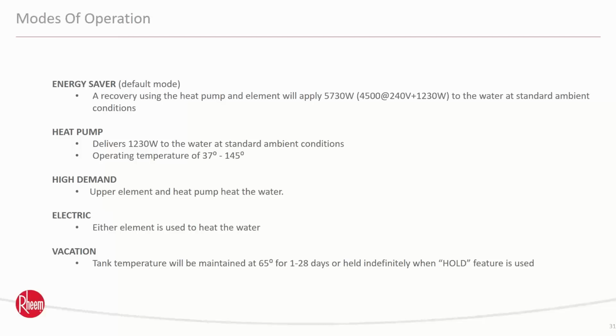The other thing is vacation mode. This thing will hold and maintain 65 degrees for up to 28 days, and that actually can be overridden to run indefinitely if you hold feature. There's a way to do that when you're on the controller.